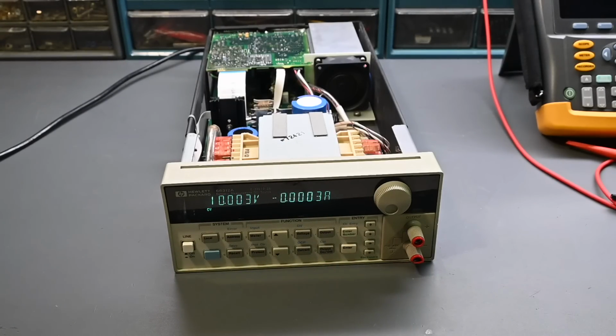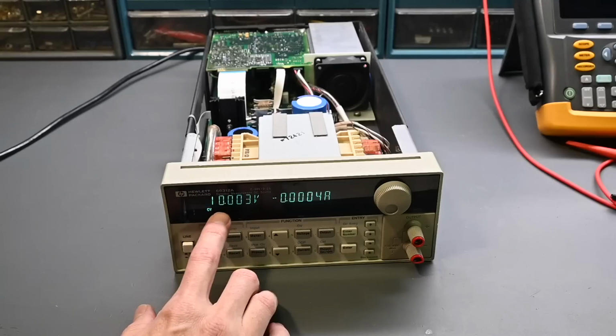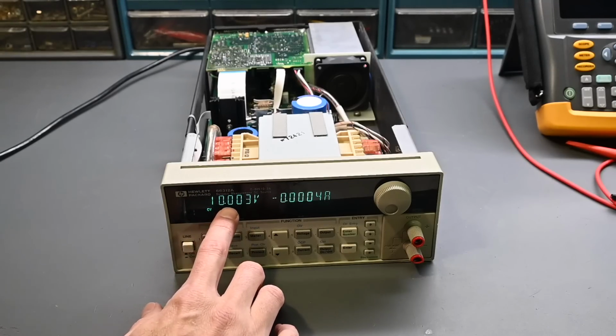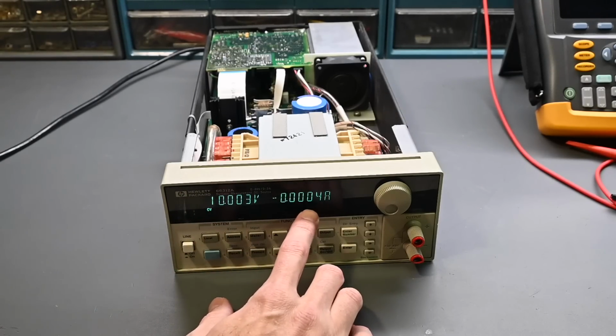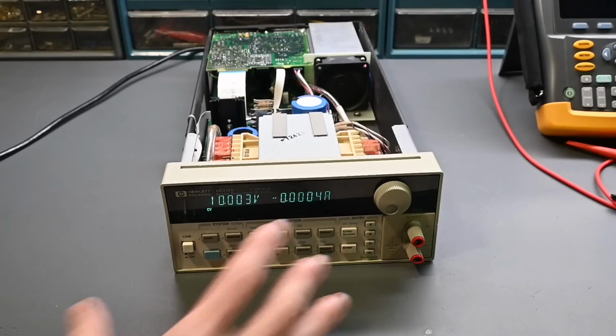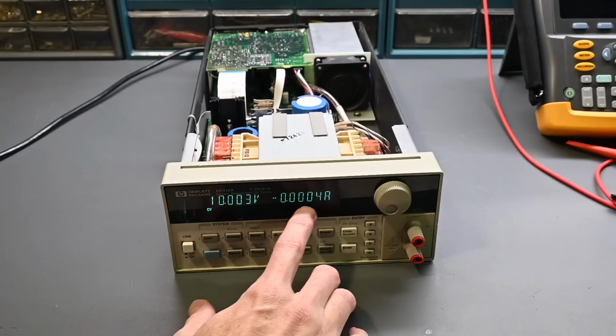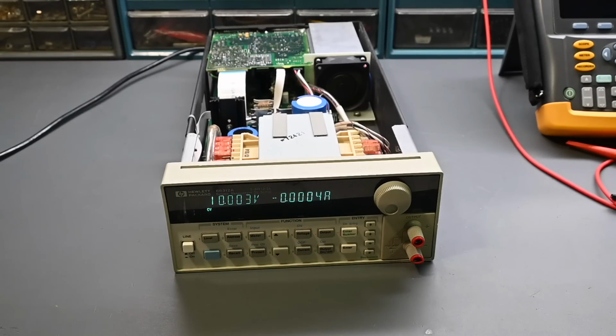Hey, how about that? That looks really good. It says constant voltage mode, that's normal. And look at the output, it says 10 volts and then just 3 millivolts, so 10.003. And the current is sitting at a very low value. It's a negative value. Now, I'm sure this needs to be calibrated. Ideally, this should be sitting at 0 over here. But this looks really promising. It's not hunting around. The value is very, very stable. So off to a good start.